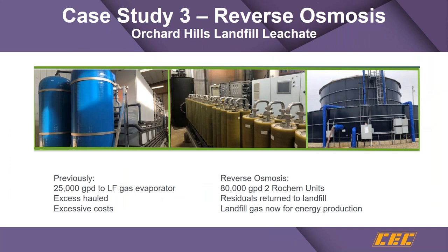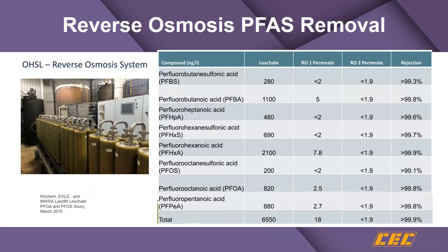Orchard Hills Landfill has a reverse osmosis system. They had a plant improvement — the original system had a 25,000-gallon-per-day gas evaporator, which was replaced with an 80,000-gallon-per-day Rochem reverse osmosis unit with residuals returned to the landfill. They have significant removal results, with virtually all PFAS constituents down to low single digits, and the system has been in operation for several years.